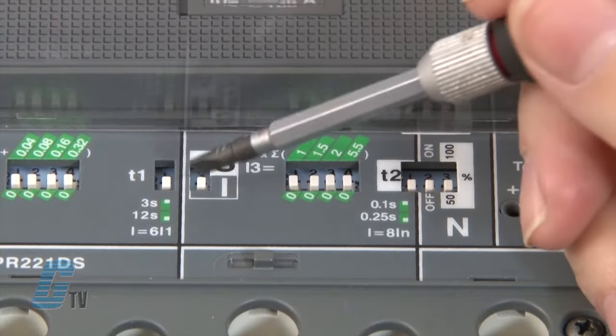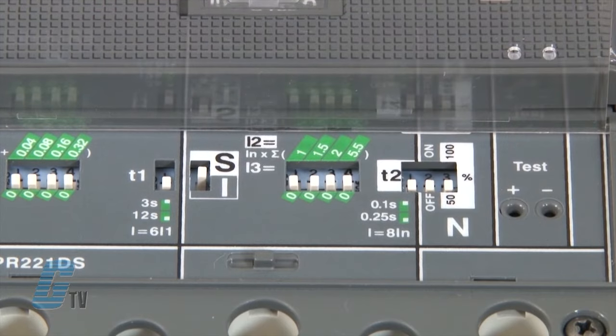When the S function is selected, the dip switches at T2 will determine whether the trip time is set to one tenth of a second or a quarter of a second.